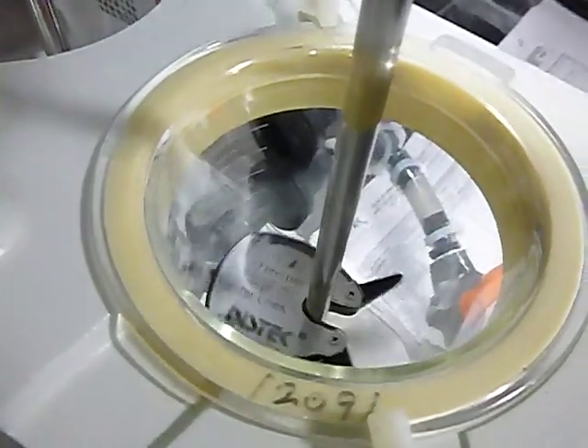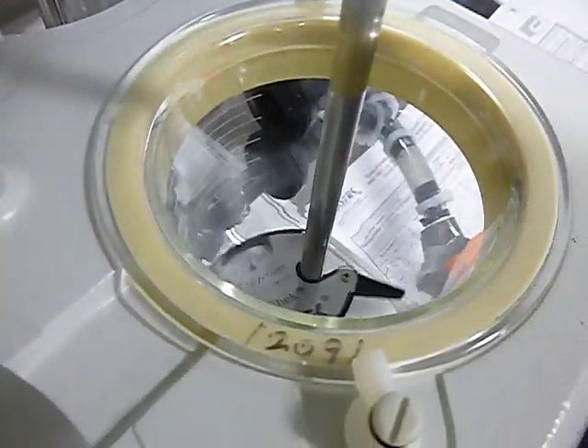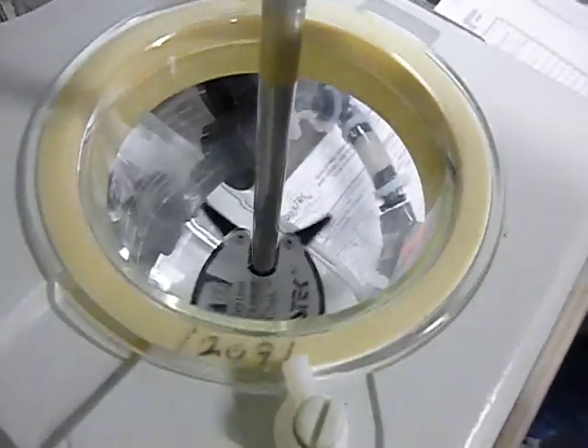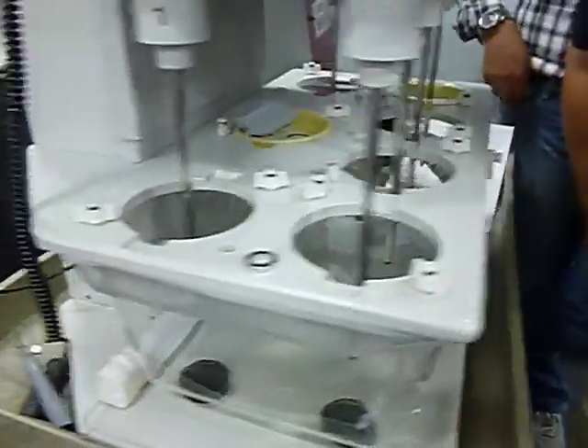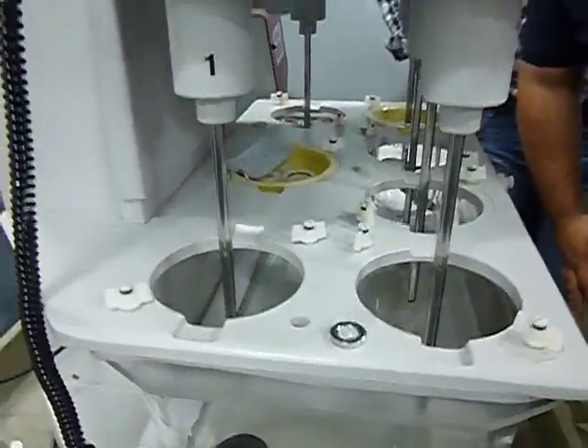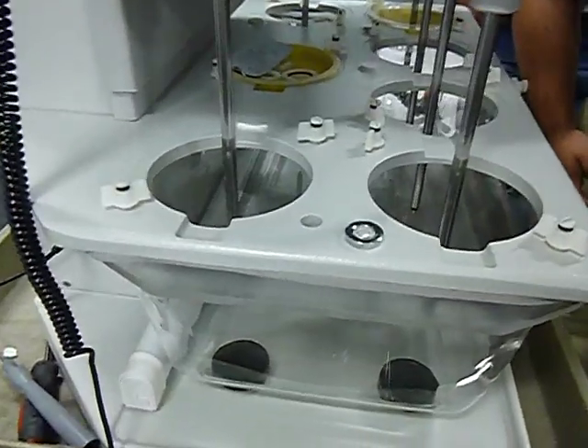So any reading you get off of that, as I indicated yesterday, from a dot, that tells you maximum deflection. The reason you cut it in half is because you're reading from the center point. So you're reading one side, and then you're also reading the other side. And whatever that deflection is, you have to cut it in half because of the way that it reads, so that it's divided by 2. That's a 1 millimeter deflection right now that I'm seeing, so cut that in half. I would put down in the document 0.50.